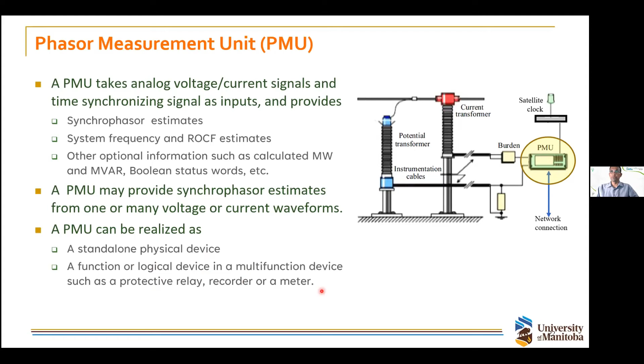So if you look at the function model of a PMU, of course, you need to take analog signals, currents, and voltages. And also you need the signal from a GPS receiver. Since all this processing happens in the digital domain, you need to sample these analog inputs. But before sampling, typically you have to do some anti-aliasing filtering to remove the high frequency noise.